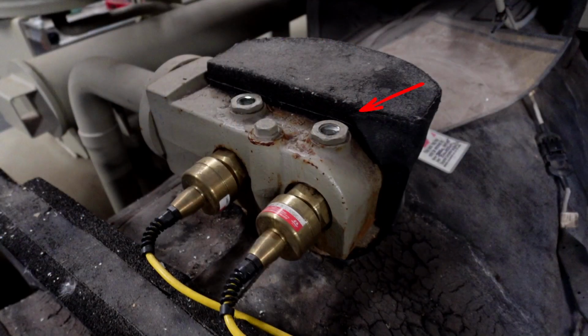Now, as that scales larger, the larger WMC series by Daikin has a dual head assembly, just like what we saw with that Trane RTHD. So that's what this one here is. This is off of an RTHD screw compressor. So these are single circuit systems that are running a large volume of tonnage.